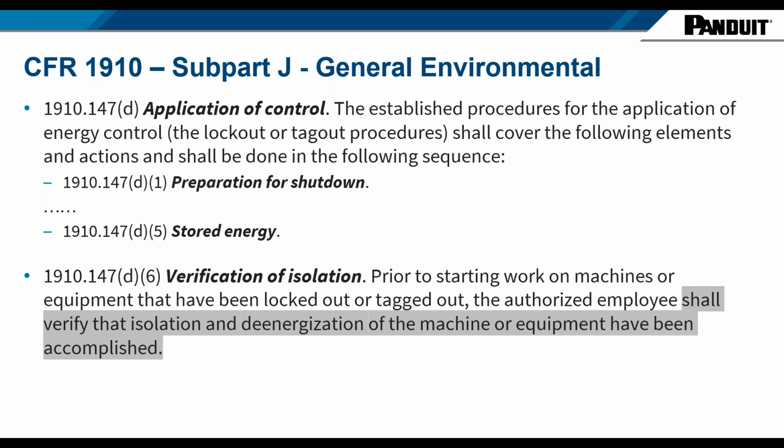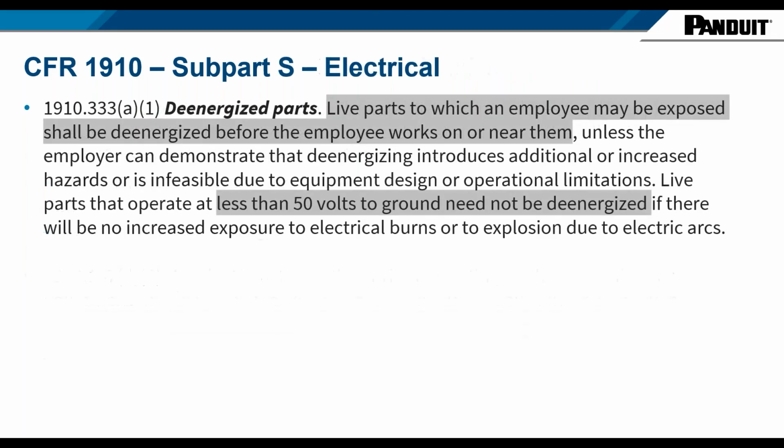The authorized employee shall verify that isolation and de-energization of the machine or equipment have been accomplished. So they're not saying how to do it, they're just saying what needs to happen. And again, this is the regulation. You have to do this. That's why it says shall. That's a very important word in standard speak. It's not a you should or you will. It's a shall, which is a requirement. So you shall verify that it's de-energized prior to being worked on.